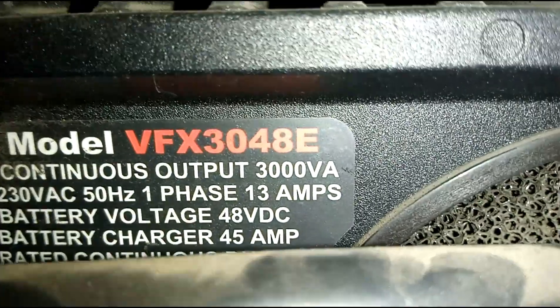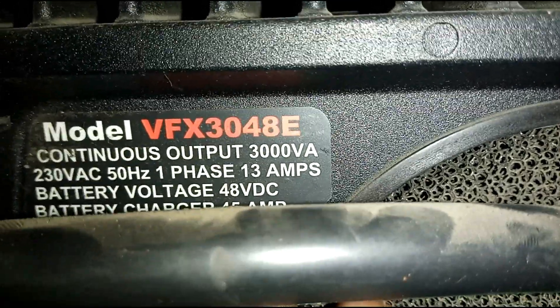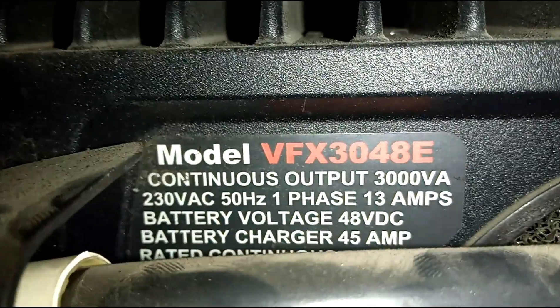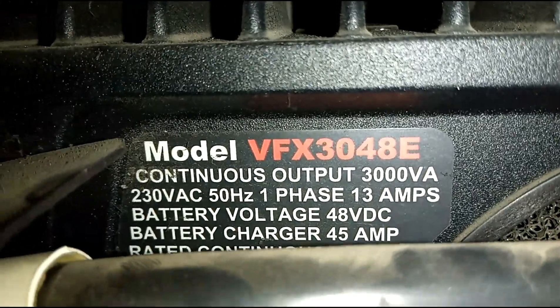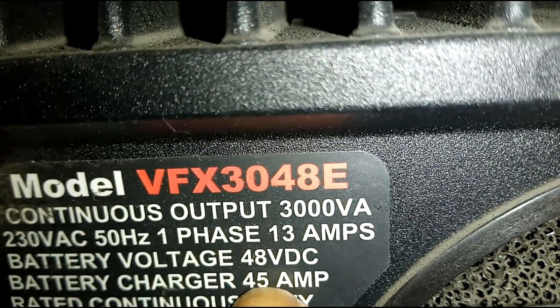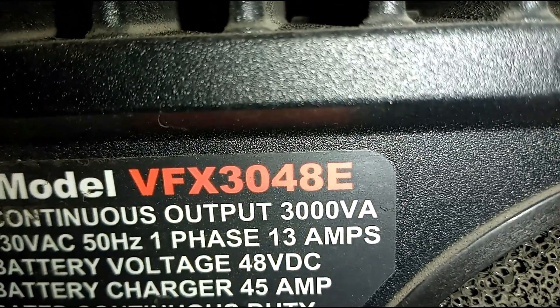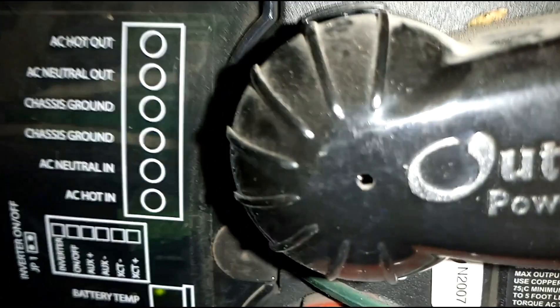An inverter will take DC and convert it to AC. This inverter is more of a backup power supply. It has the grid input where 230 volts is fed in. While the grid power supply is up and running, it turns on the 45 amp battery charger to charge the battery. When the grid voltage goes off, it automatically switches to the battery and converts it to AC.